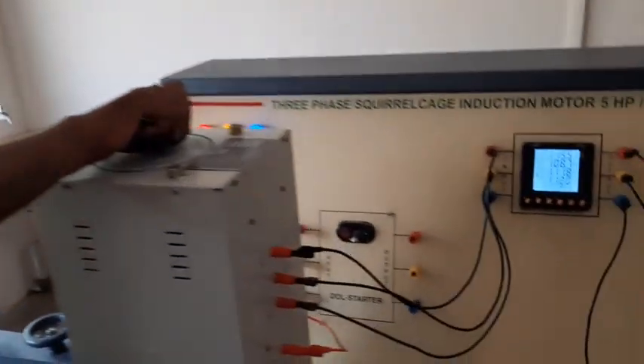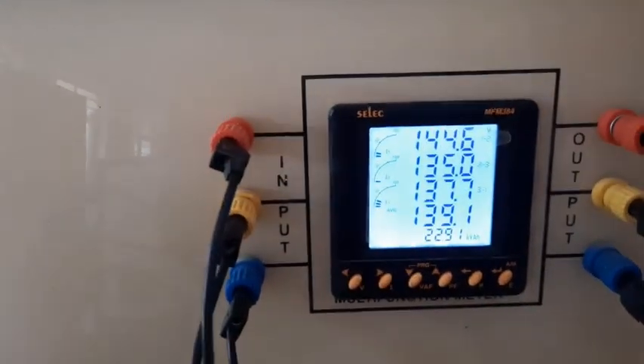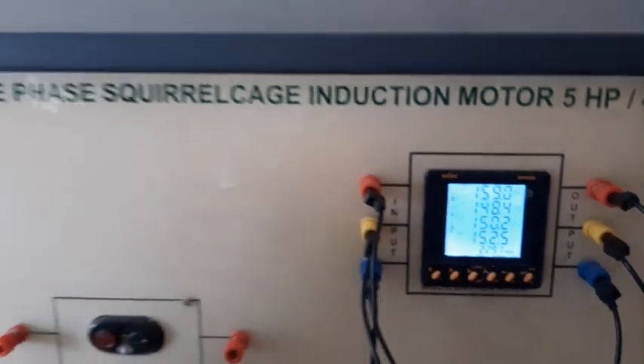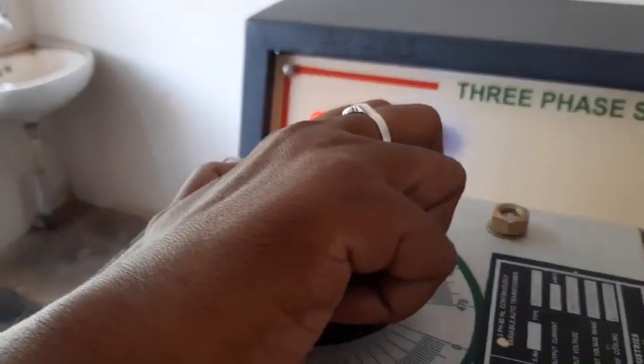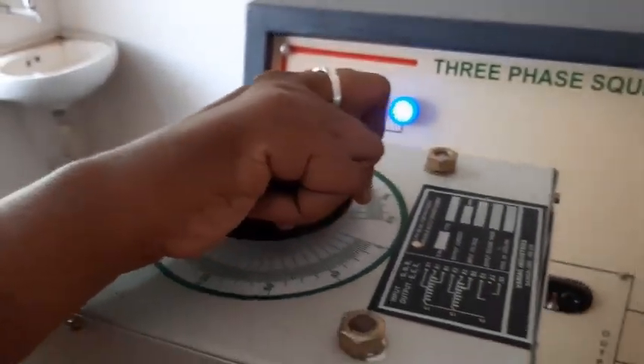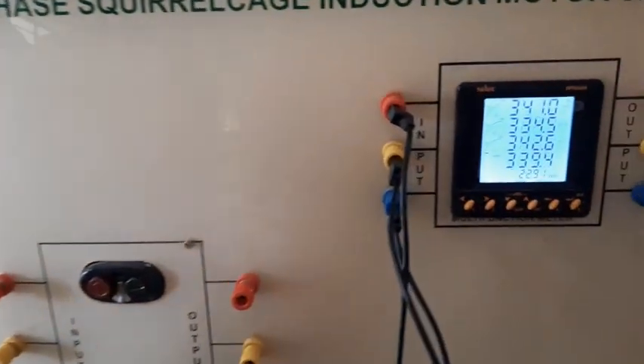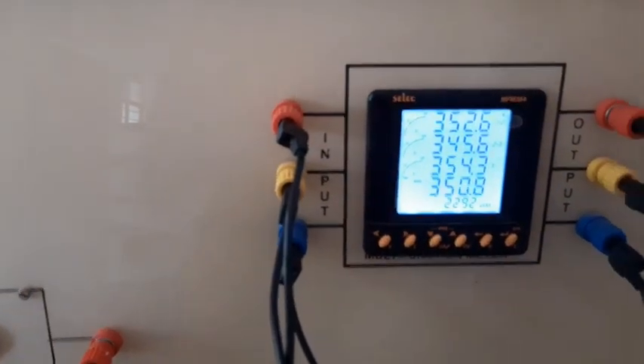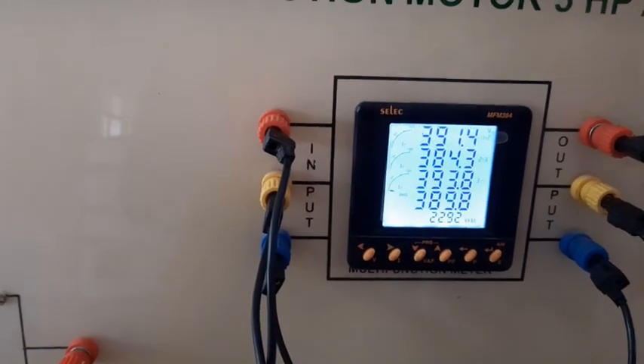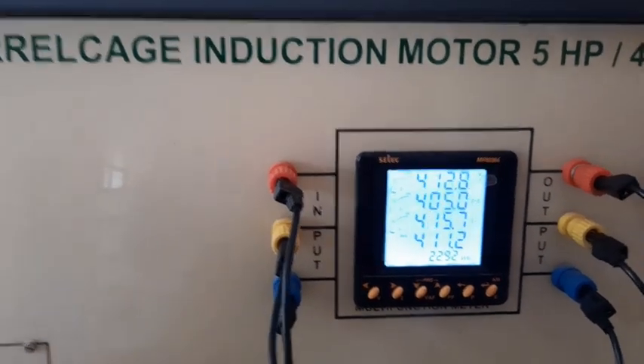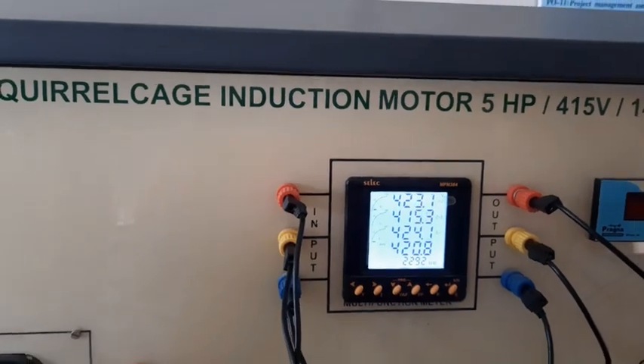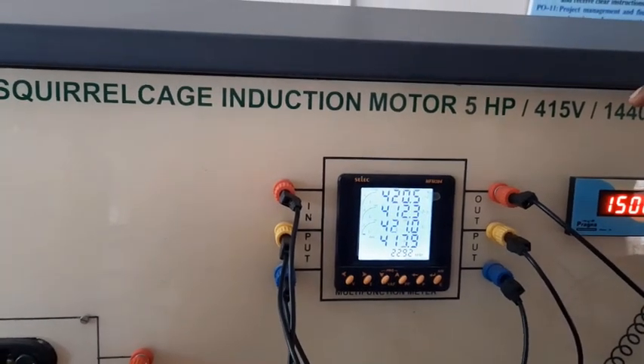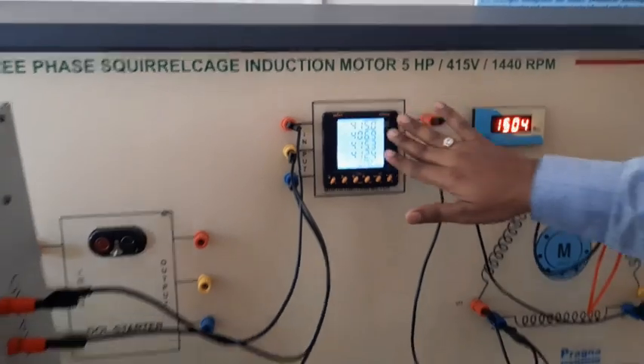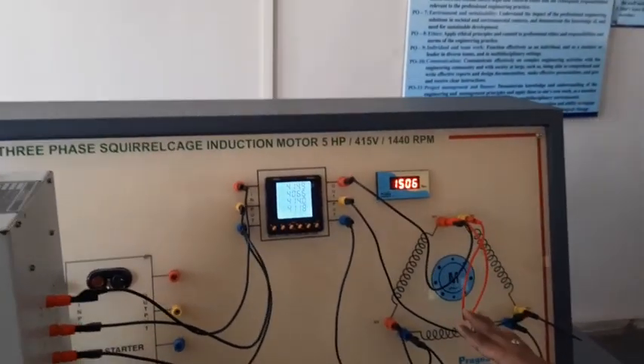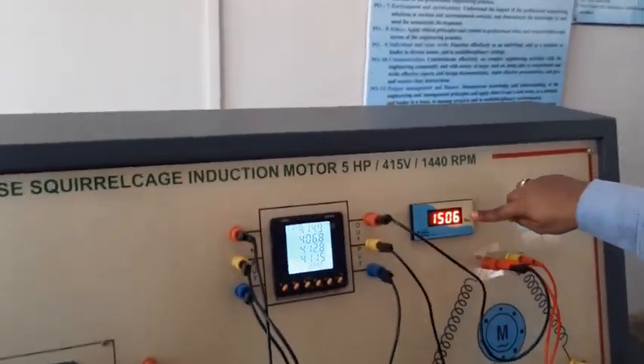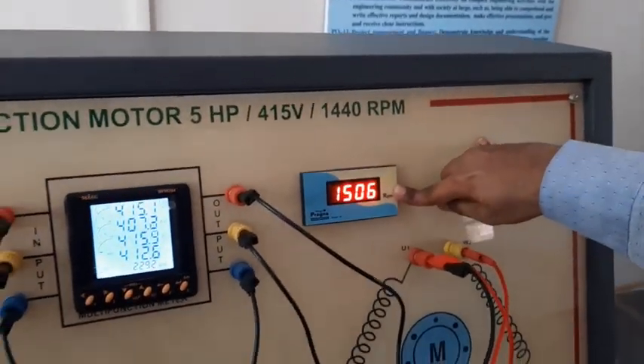Watch this one here, the voltage goes on rising. So give a supply of 415 volt. Okay, this is enough, so slowly come down. Okay, this is now 415 volt. This is the rated voltage of the motor. The speed is 1500 rpm, 1506 rpm.